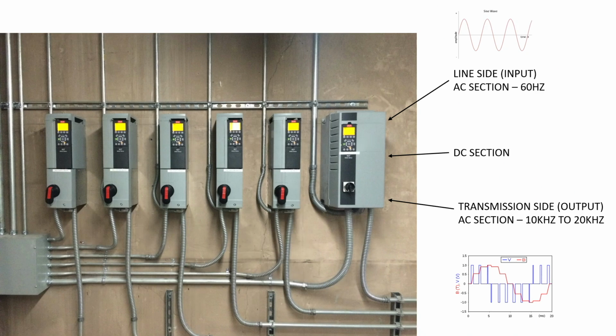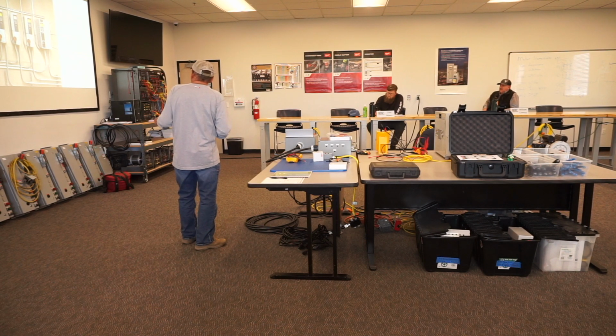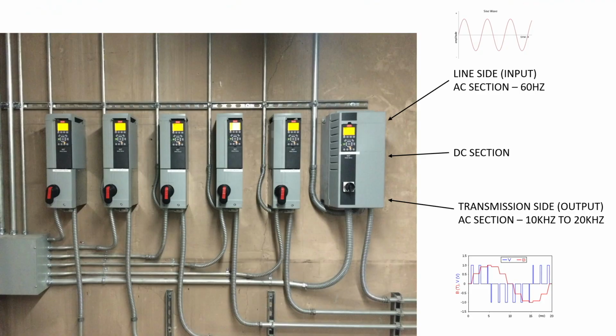So, here's another facility, Washoe County, and as you can see, a proper installation. The input is all in a single conduit, and the output goes to each individual motor. Proper installation. Still having problems though. So basically, your input is AC. There are three sections in a drive. You've got your input, your 60 hertz. You've got the center section, I call it, which is the DC section. And then you've got the output section, which I call the transmission side because of the frequency of the drive.